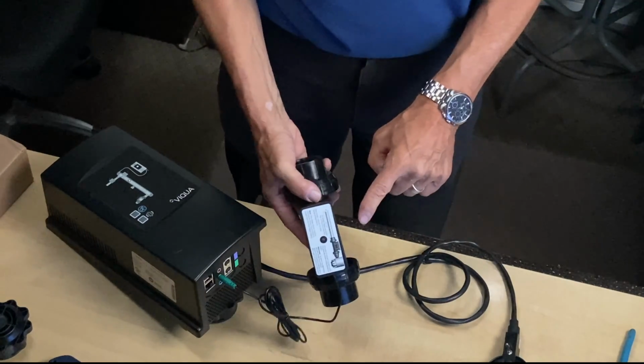Now this does have a flow restrictor built in. So since this is a 10 gallon per minute system, this will restrict the flow to 10 gallons per minute. If the flow sensor were to fail, it would also signal the controller, and the controller would go into alarm to tell you that it's failed.